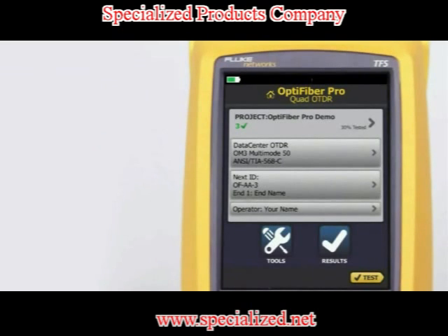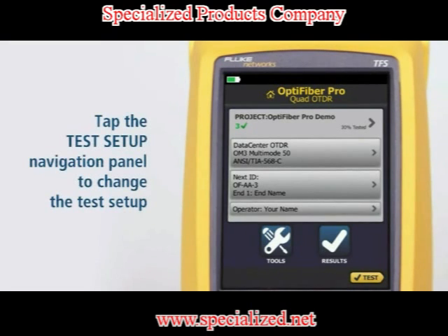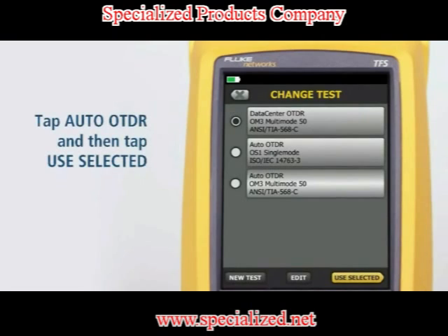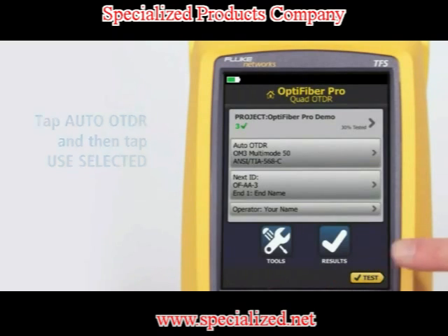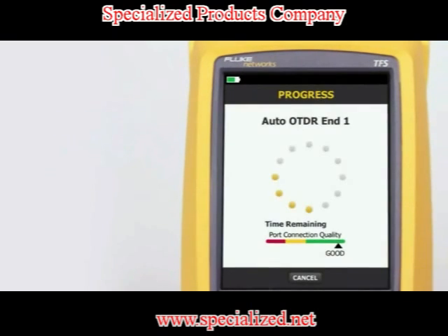The Auto OTDR test mode automatically selects settings that give you the best combination of test time, dynamic range, and resolution. It provides the best view of the events on the cabling. This mode is the easiest to use and is the best choice for most applications. The previous test was run using the Data Center OTDR setting. Tap the test setup navigation panel to change the test setup, tap Auto OTDR, and tap Use Selected. Now simply tap Test and the tester will determine the best setting to use for the fiber under test.